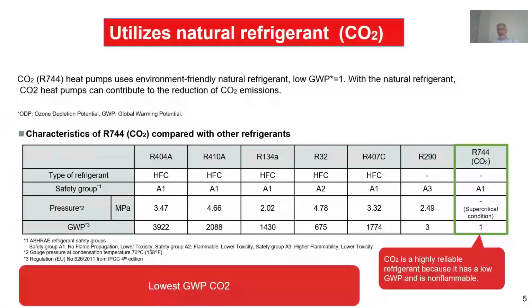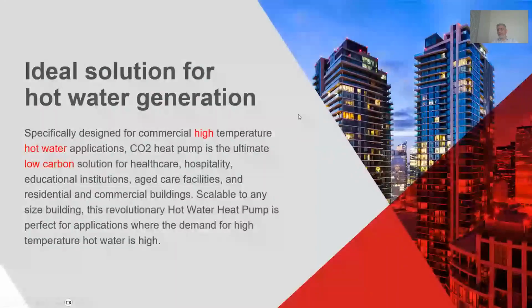Among the refrigerants available in the current market, HFCs such as R404, R410, R134 and R32, CO2 is the best among those because it is in safety group A1 and has a GWP of 1. If you compare it with all the available refrigerants, you end up with the best solution. CO2 is a natural solution if you're providing hot water for domestic use.